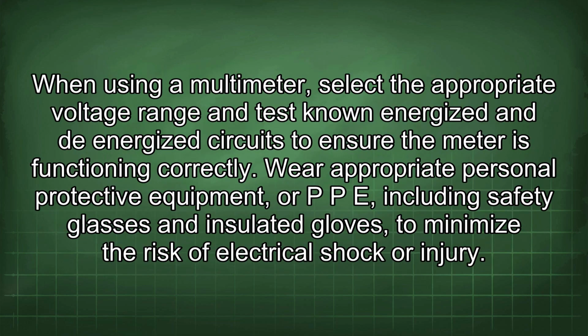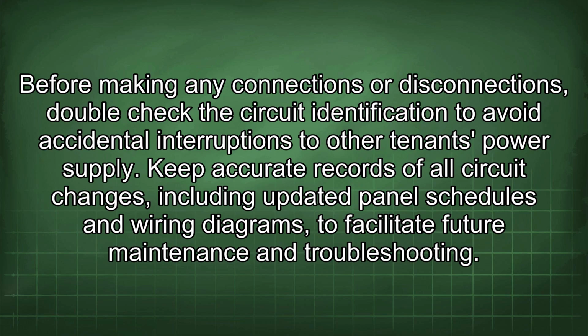When using a multimeter, select the appropriate voltage range and test known energized and de-energized circuits to ensure the meter is functioning correctly. Wear appropriate personal protective equipment, or PPE, including safety glasses and insulated gloves, to minimize the risk of electrical shock or injury. Before making any connections or disconnections, double-check the circuit identification to avoid accidental interruptions to other tenants' power supply.